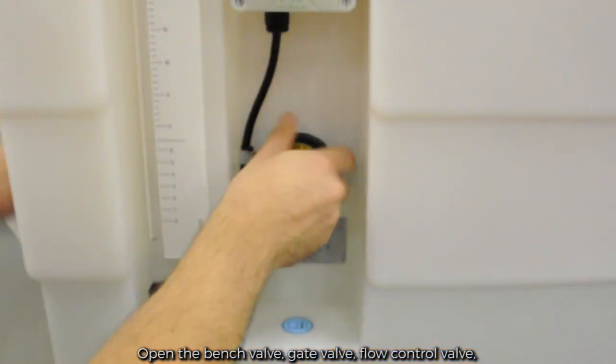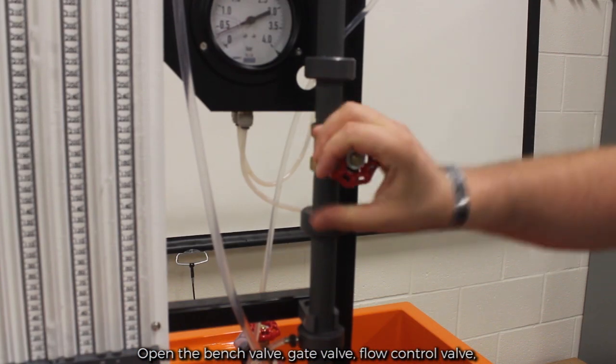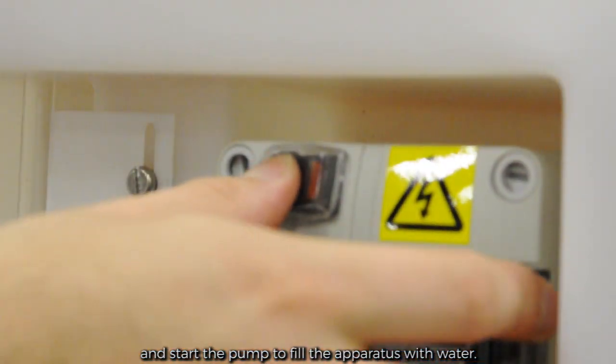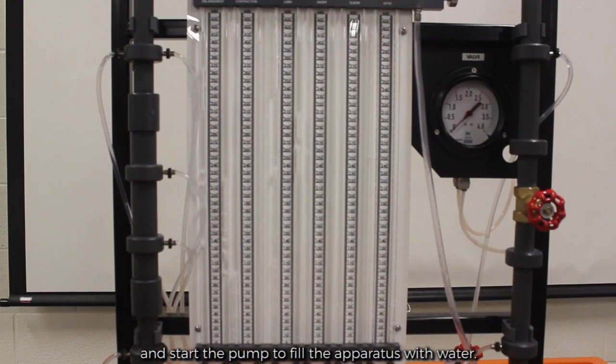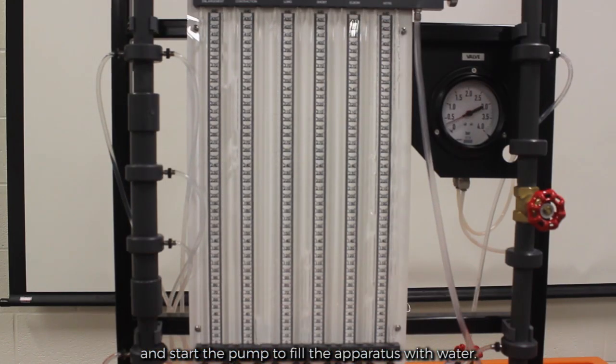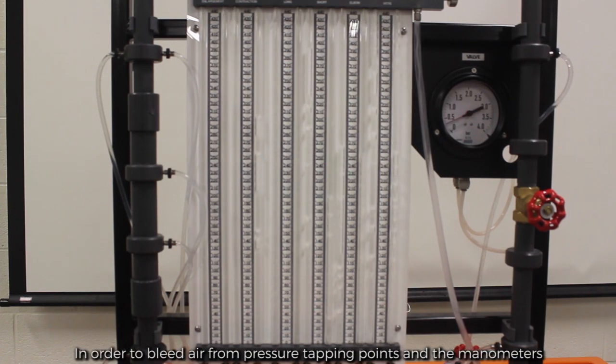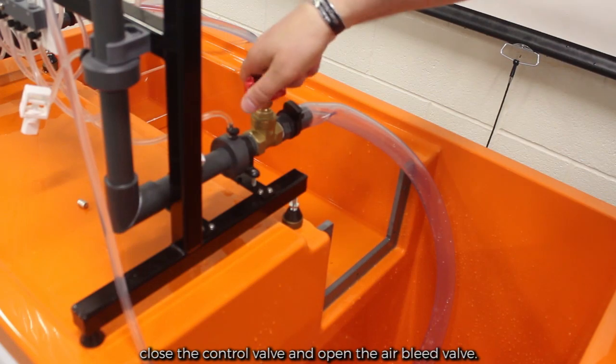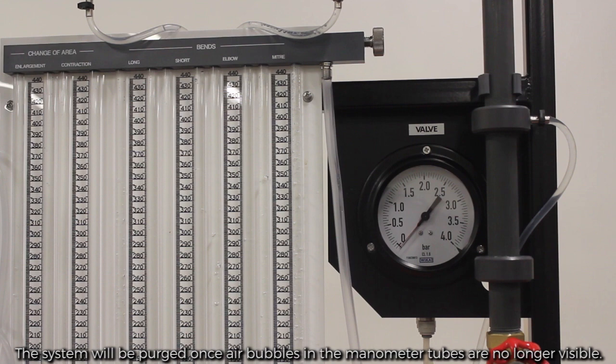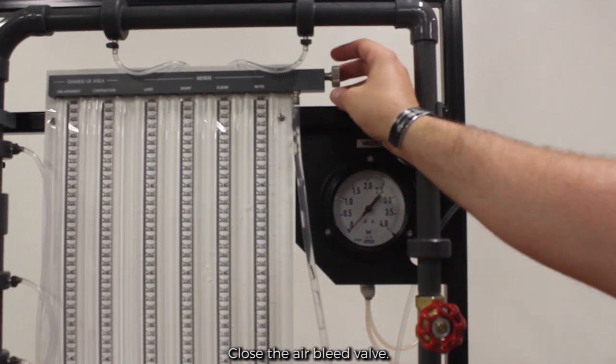Open the bench valve, gate valve, flow control valve, and start the pump to fill the apparatus with water. In order to bleed air from pressure tapping points and the manometers, close the control valve and open the air bleed valve. The system will be purged once air bubbles in the manometer tubes are no longer visible. Close the air bleed valve.